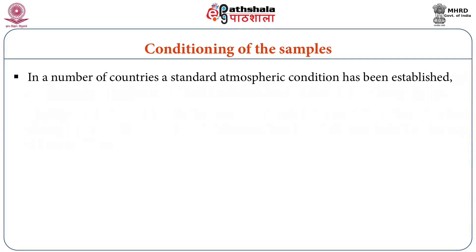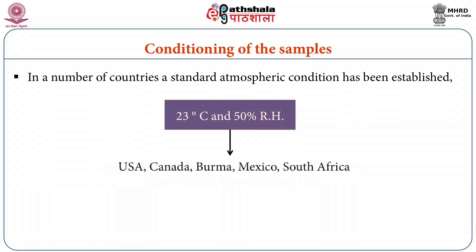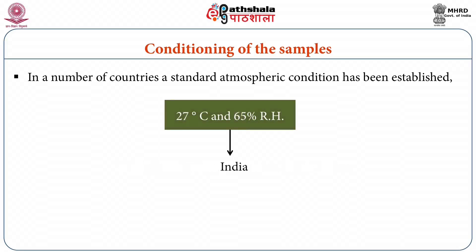In a number of countries, a standard atmospheric condition has been established: 20 degrees centigrade and 65 percent RH in Argentina, Australia, Belgium, France, Germany, Netherlands, New Zealand, and United Kingdom. Whereas 23 degrees centigrade and 50 percent RH in USA, Canada, Burma, Mexico, and South Africa. In India, the prevailing standards are 27 degrees centigrade and 65 percent RH.